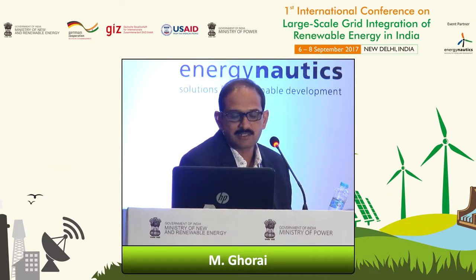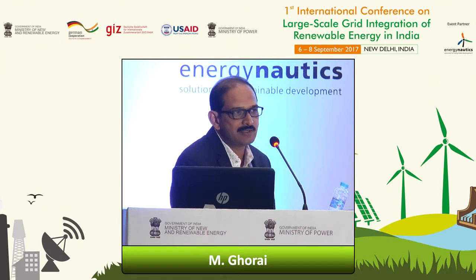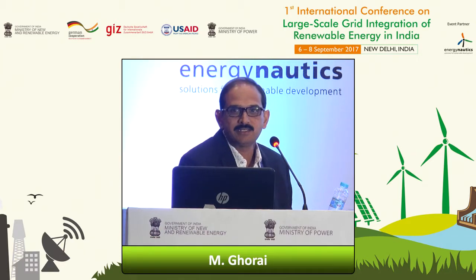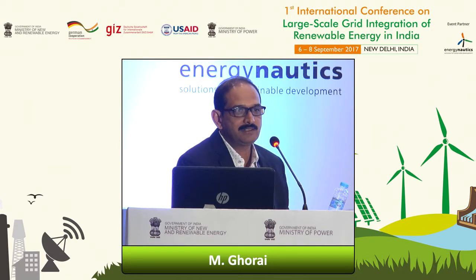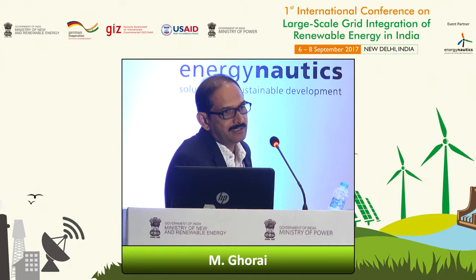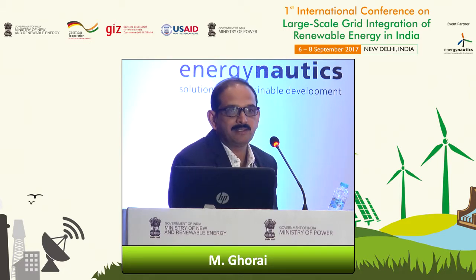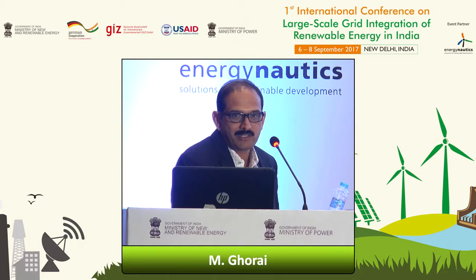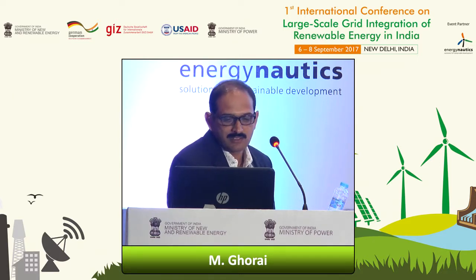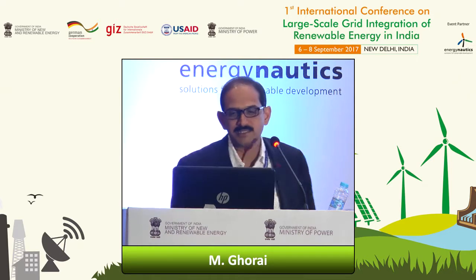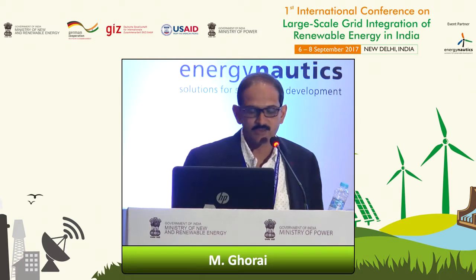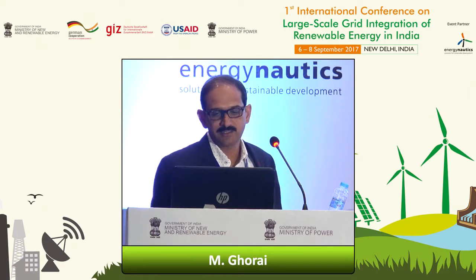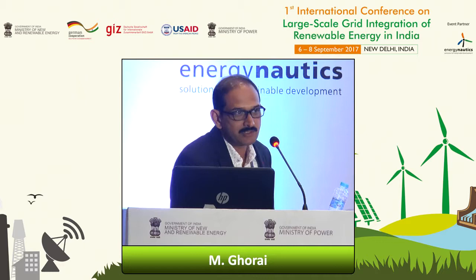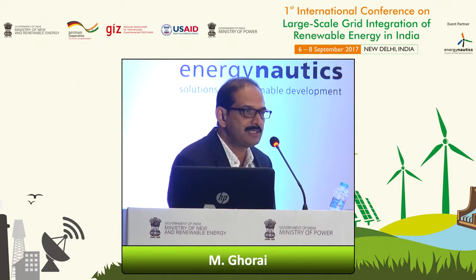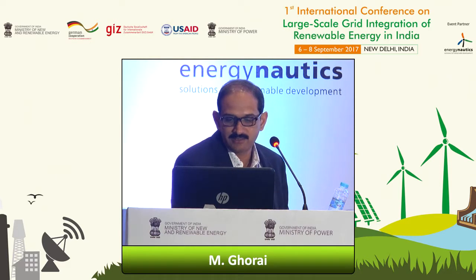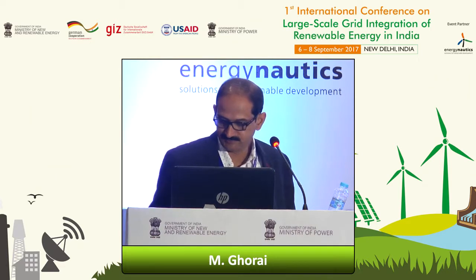So this all drives the operator to issue some grid codes, where they would like to see all these renewable energy power plants as conventional power plants. At the point of common coupling, they want to see the entire renewable plant as a conventional plant. That's why they come out with the grid codes. These grid codes talk about the voltage ride through or dynamic capability, then the power factor capability, the control objective, and power quality, flicker and other things, and how you validate all these compliances.